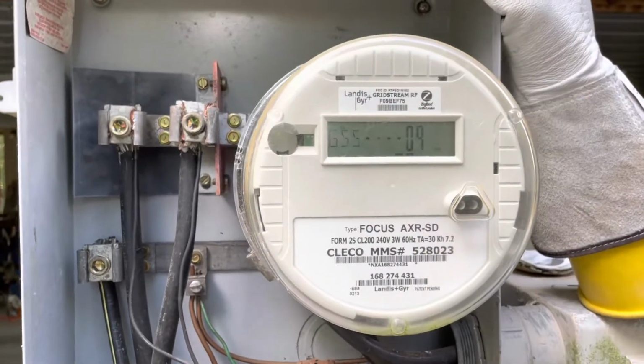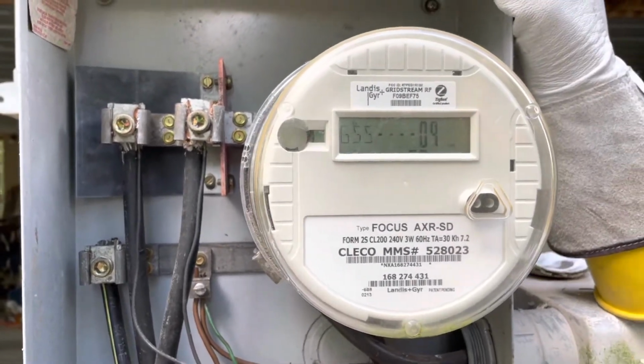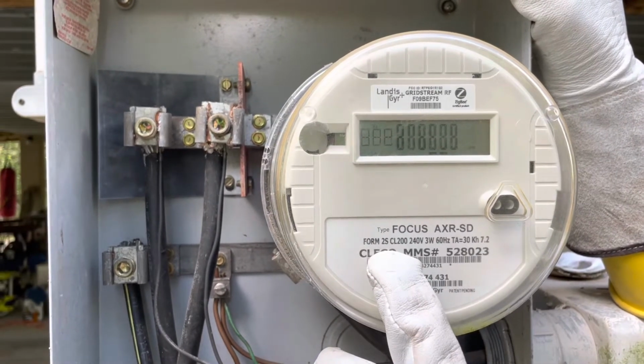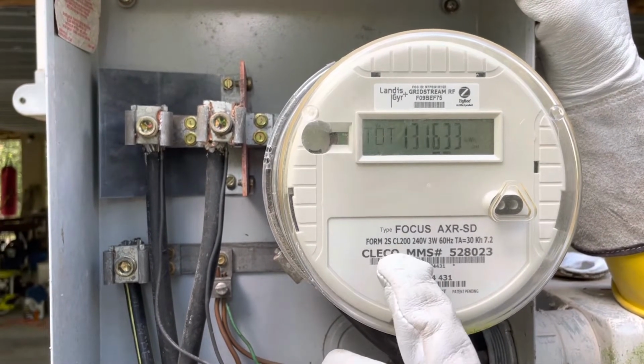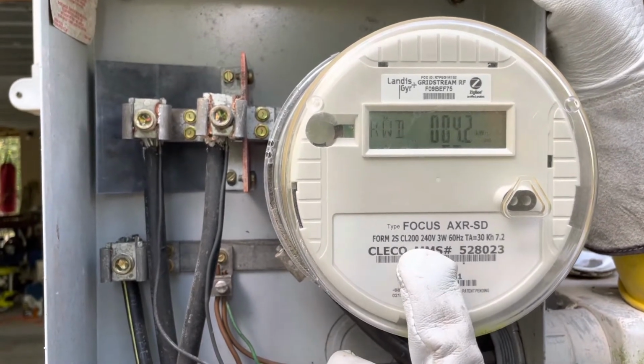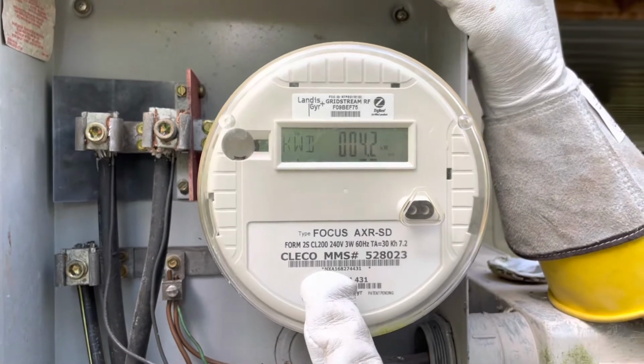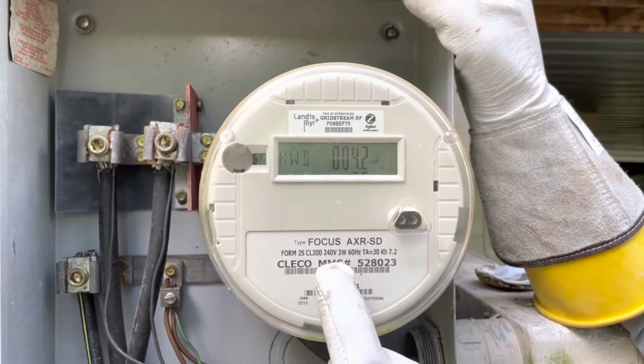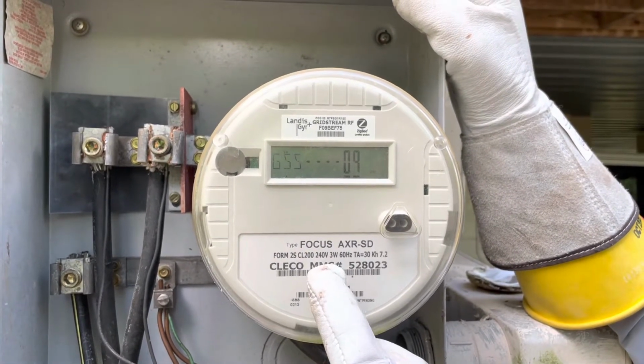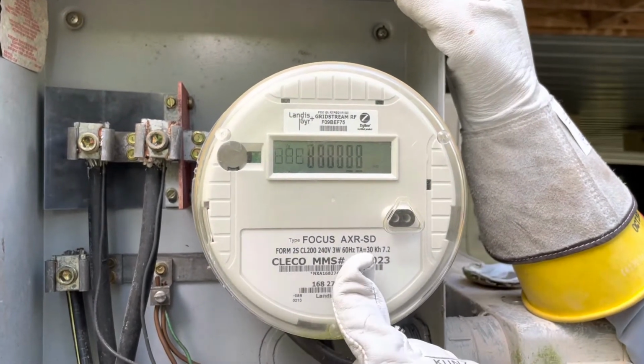Let's focus on the meter itself and the type of meter. This is a Focus AXR meter. It's a Form 2S, which means a 2S is for a single phase 120/240 service. It's a class 200, which means this meter is rated for up to 200 amps. It's a 240 volt meter. You need 240 volts to meter this site correctly. This is a 3-wire service, 2 hot legs and a neutral.